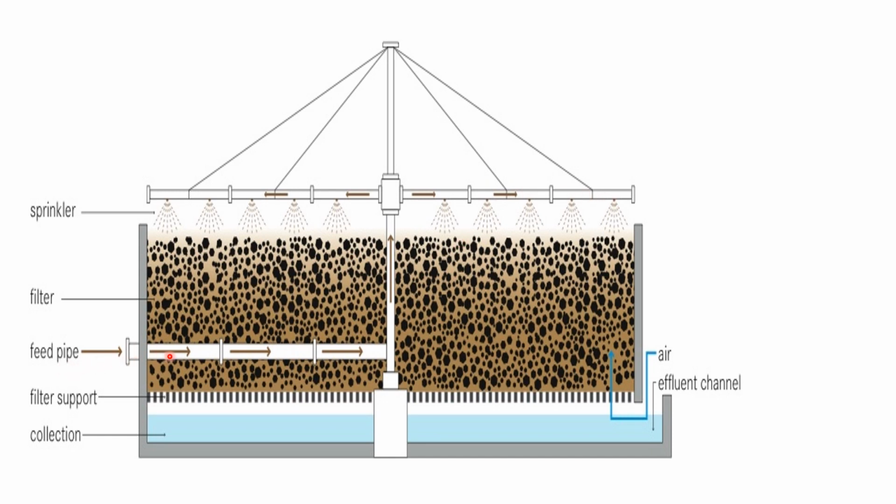So we feed sewage water through the inlet, it moves upwards, and as this rotating distributor rotates, these two side arms also rotate, and this sewage water is uniformly spread into this filtering medium. Then it moves downwards. As it moves downwards, the aerobic bacteria present inside this filtering medium carry out the aerobic oxidation of sewage, and after aerobic oxidation the products carbon dioxide and nitrates escape from this filtering medium, and the treated sewage water is collected in the effluent channel. So we can collect the treated sewage from this effluent channel.